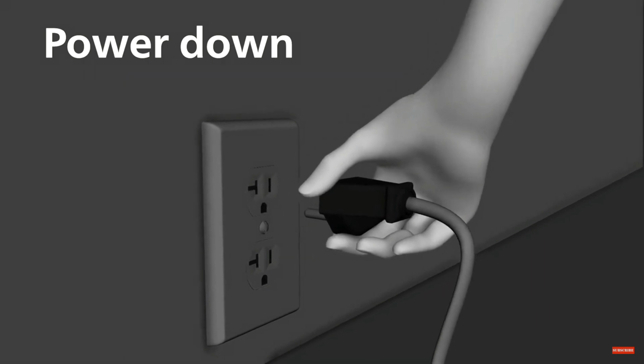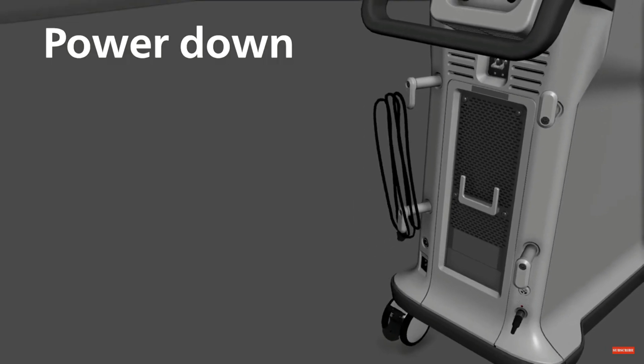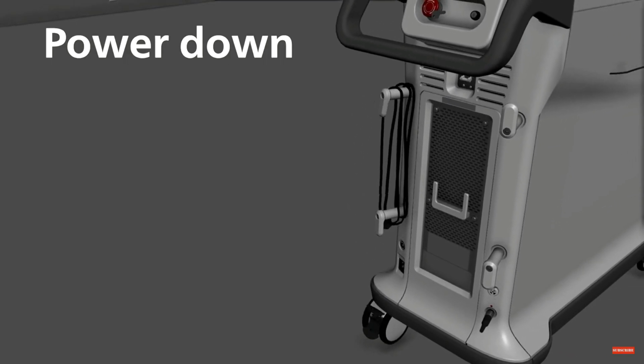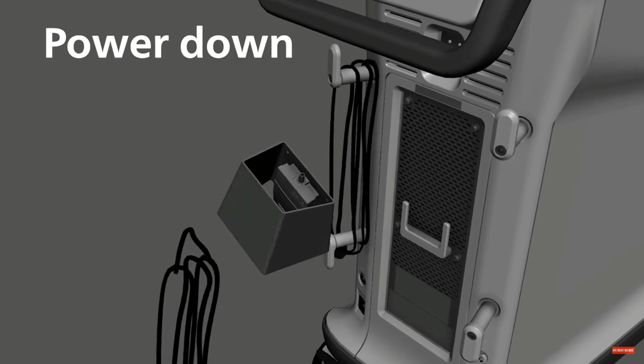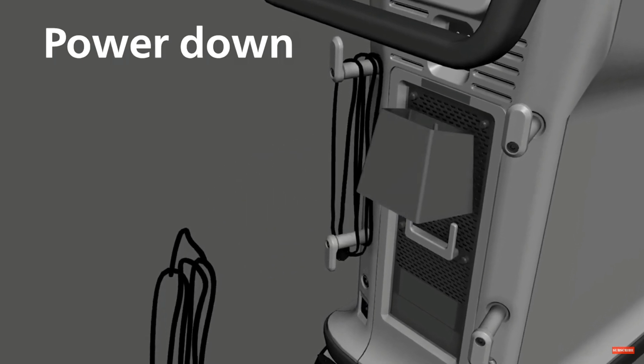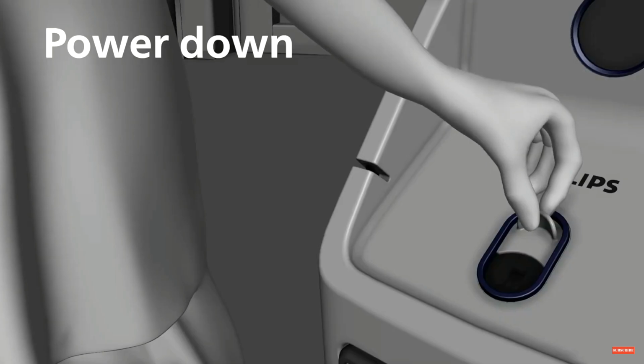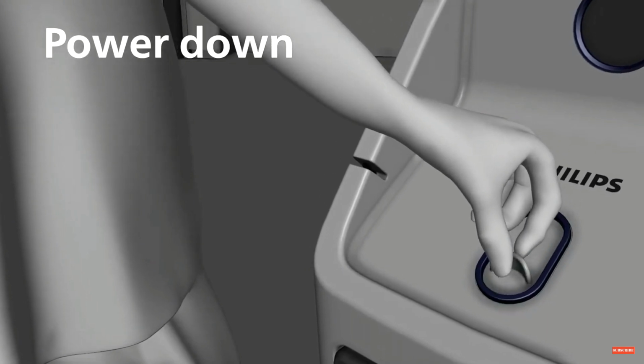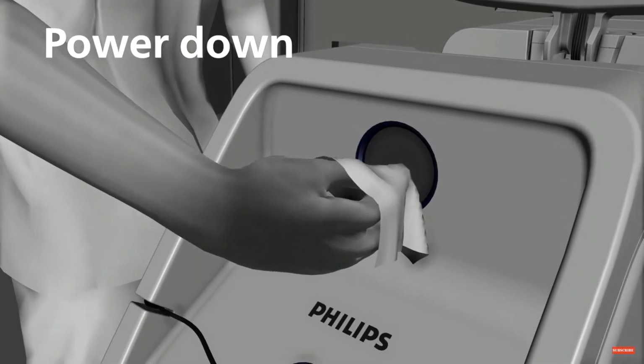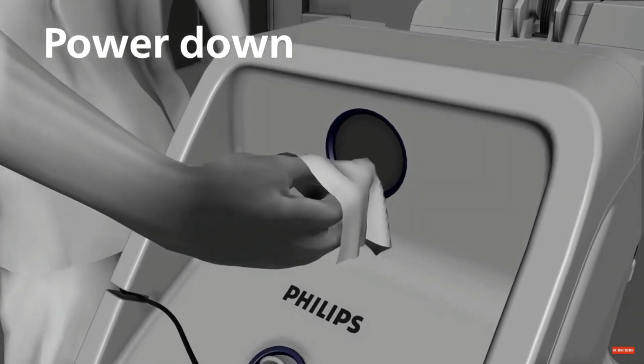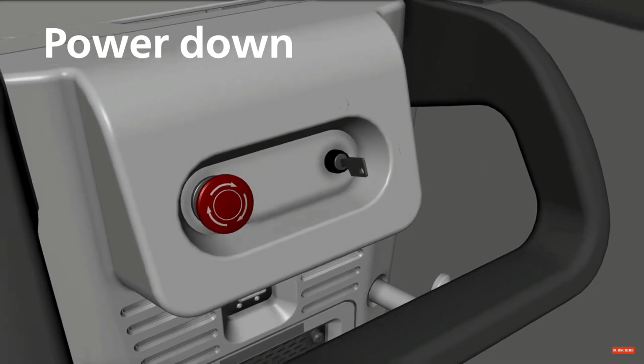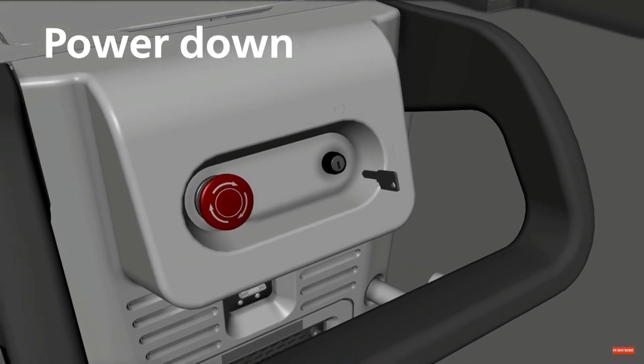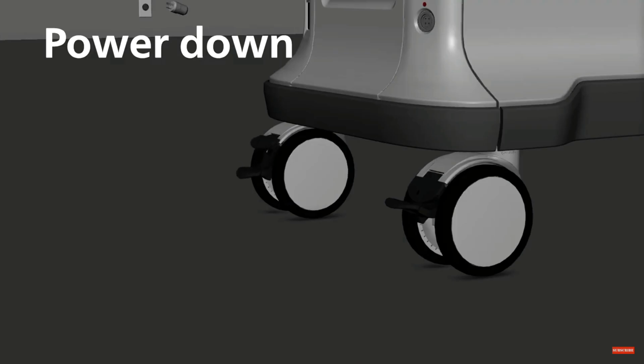Disconnect the power cord from the wall receptacle and store it on the cable management wraps at the rear of the system. Then disconnect and store the foot switch at the rear of the system. Close the catheter connector door and clean the detector face with alcohol prep. When not in use, remove the key to protect the system from unauthorized use. Return the system to your storage location and lock the rear wheels.